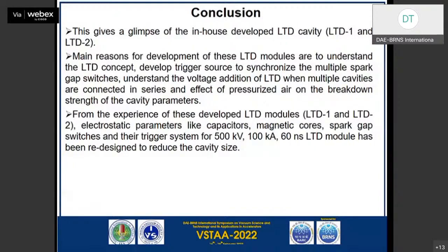Why in LTD2 waveform is there ringing? In waveform 1 it is very clear, but in the second there is ringing. Actually sir, first of all it is not charged to the required voltage. It is designed for plus or minus 100 kV, but since the complete system will be inside a pressure chamber which is still in fabrication, we charged it at plus or minus 30 kV only. So the load also was not in the matched condition, so there was a little bit of underdamped condition, that's why some ringing occurred. I'm not asking about the 100 kV, I'm asking about the ringing in between, the waveform is not clear in that part. It is not due to impedance matching, I guess. Actually sir, it is because it is not charged to the full voltage, so synchronization is not possible between all 30 spark gap switches.